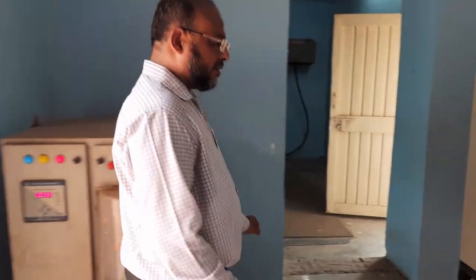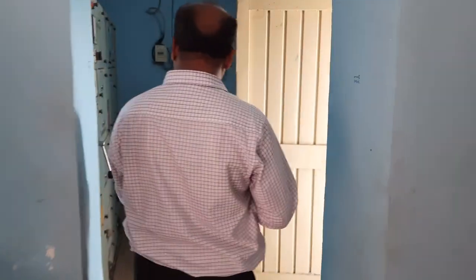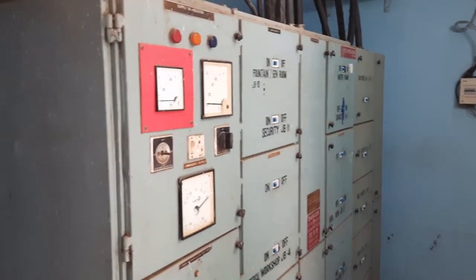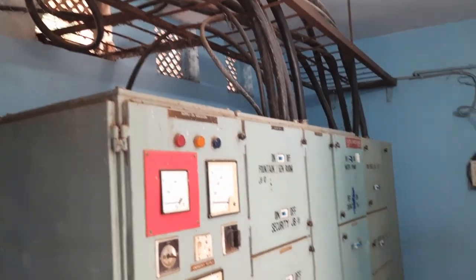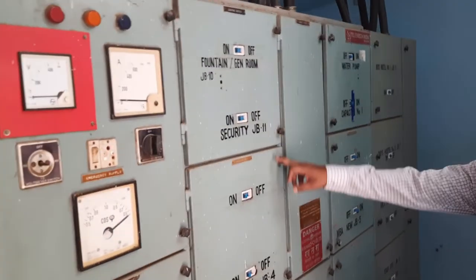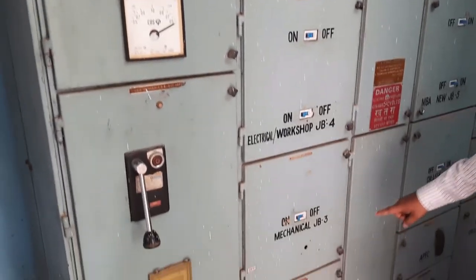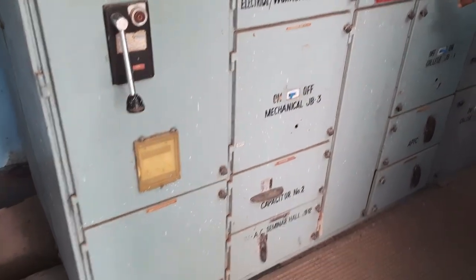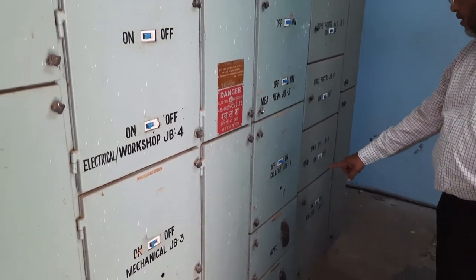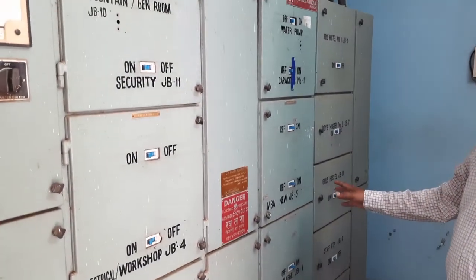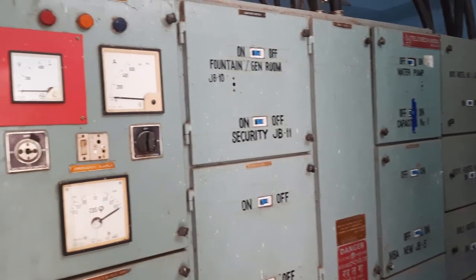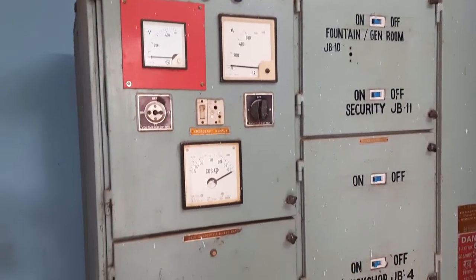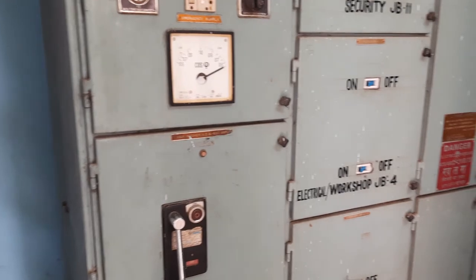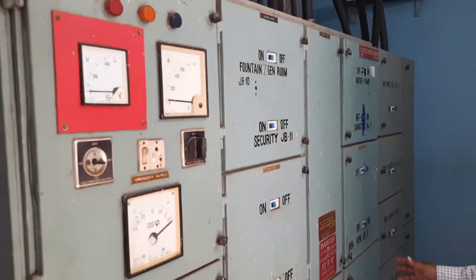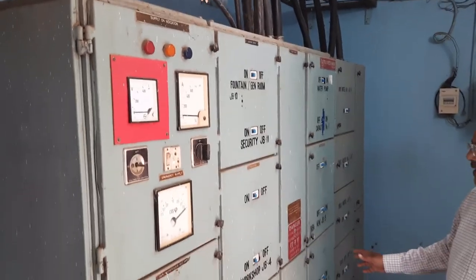Now we will look at the transformer and switching yard. This is our main panel. It comprises different feeders like security feeders, electrical and workshop feeder, mechanical buildings, administrative buildings, college 1, college 2, staff quarter, and girls hostel. So separate feeders are there. It is useful for maintenance as well as safety, and whenever there is a failure in any one of the feeders, the rest of the system will remain healthy, even under maintenance.